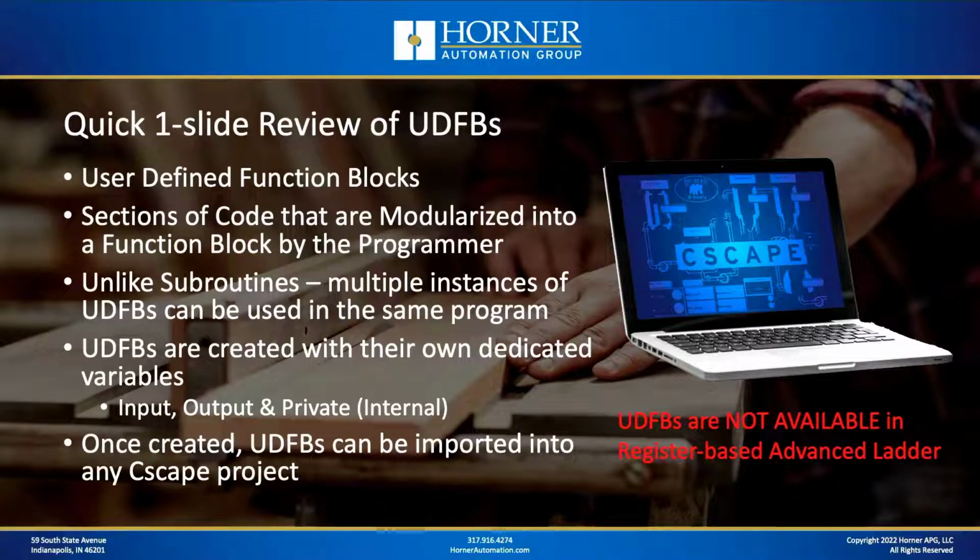Now keep in mind what we've got written there in red, and that is that UDFBs are not available with register-based advanced ladder. This is a feature that's only available in variable-based advanced ladder, sometimes we call it tag-based, or in our IEC 1131 implementations. So that may be one of the reasons why you decide to transition away from register-based and towards one of the other options.